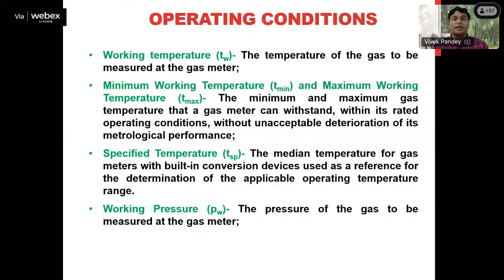Similarly, there is a specified temperature, which is a parameter specified by the manufacturer for the temperature correction device. Whenever a gas meter is being used for the measurement of the quantity of gas, and the temperature of the gas deviates from the specified temperature value, how much correction should be made? For that, there is a fixed specified temperature given by the manufacturer. That specified temperature is prescribed by the manufacturer, and accordingly the temperature correction will be done.